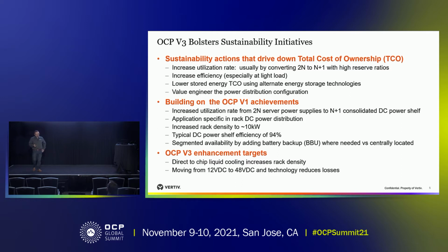The other thing we see in the V1 improvement is, we were right around 10 kilowatts per rack in that design. Now in V3, we're implementing liquid cooling. If you have a chance to come over to our booth, you'll see some liquid cooling rails on the back of a V3 rack, and you'll see how that's implemented. Implementing liquid cooling can now increase your capacity. So from a standpoint where you might have had 3 racks, you may now be able to do the same capacity in a single rack. Using liquid cooling will get you there.